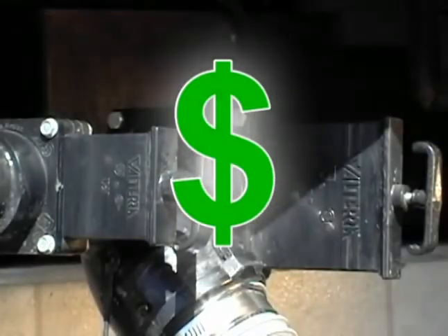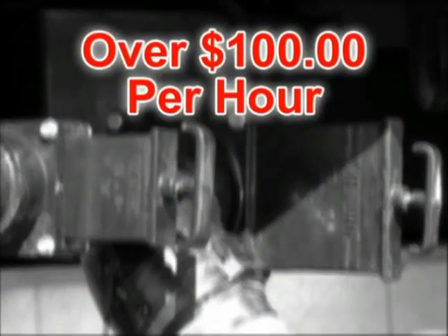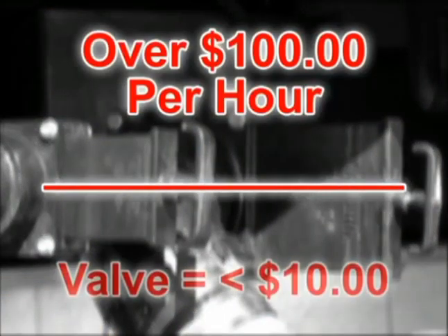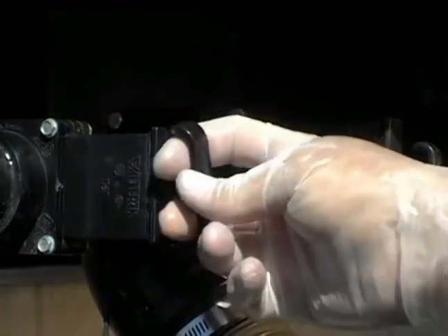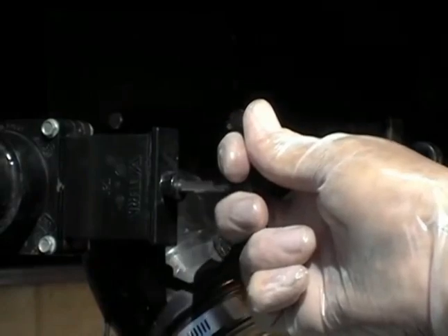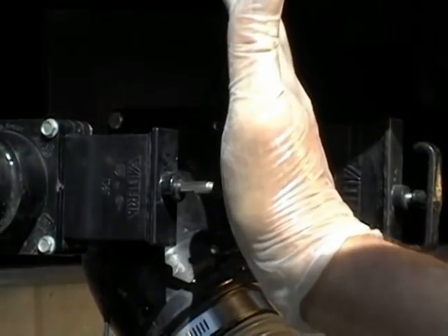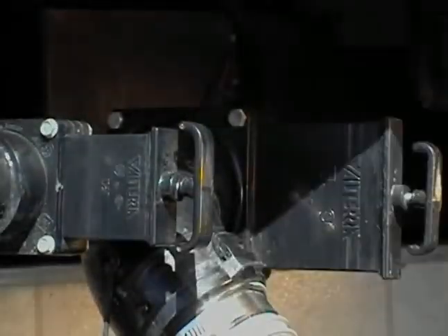When I get called out on these cases, I charge time and a half. It costs over $100 an hour to have me do the repairs, and the valve costs less than $10. This unit needs new valves. See how hard they are to operate? When the tanks are empty and you can't open and close them easily, have them changed.